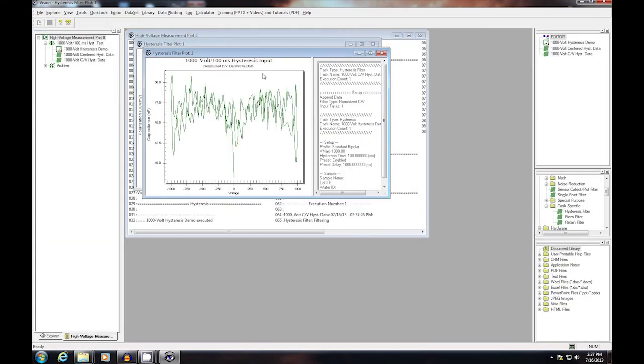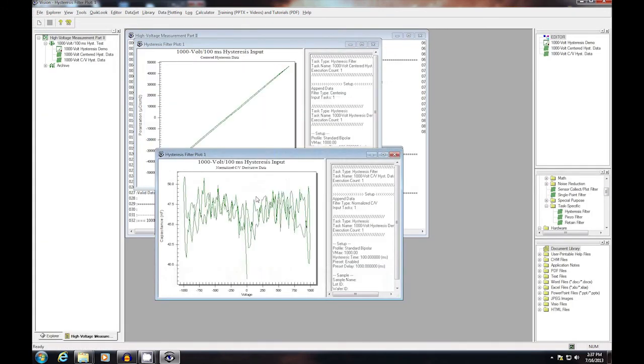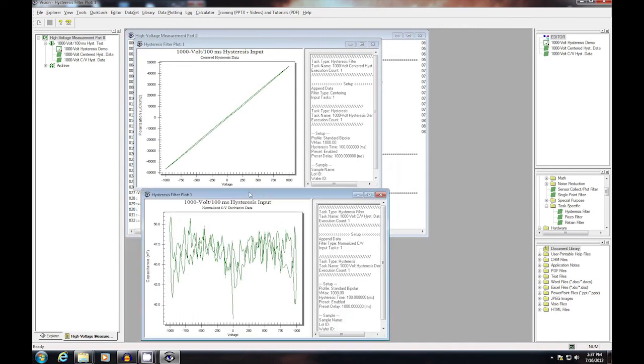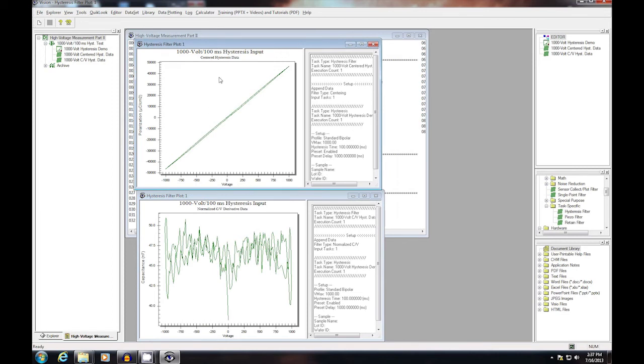When the measurement is complete, each of the filters provides a plot. The first plot is of the standard hysteresis data, polarization as a function of voltage. The second plot is the derivative of the first plot, presenting capacitance as a function of voltage.